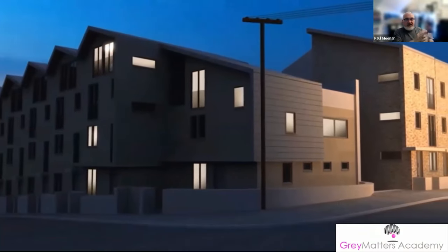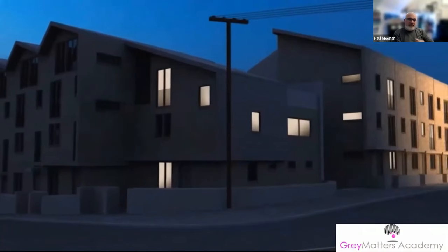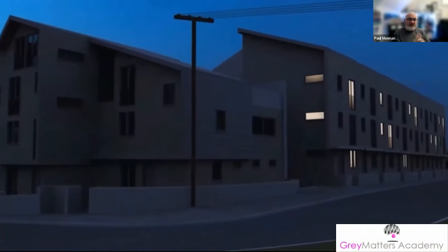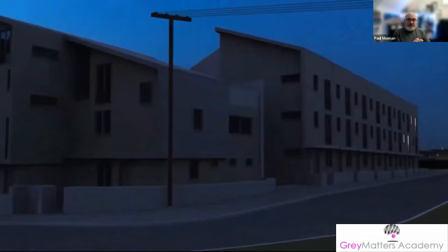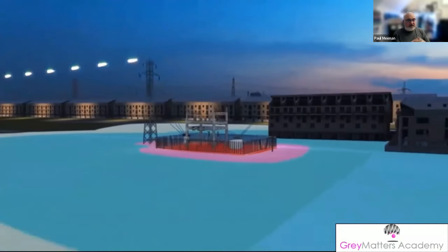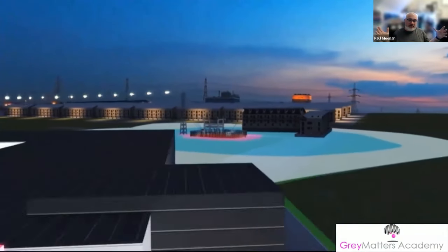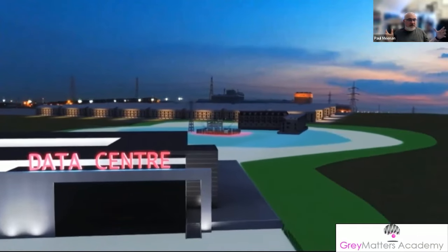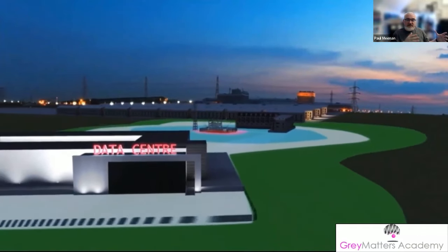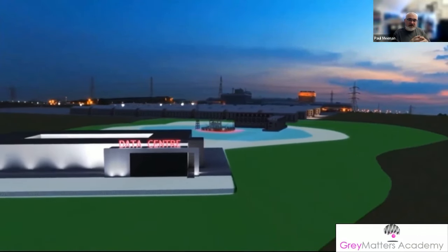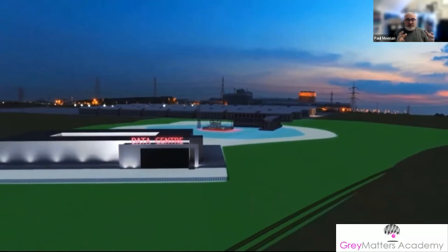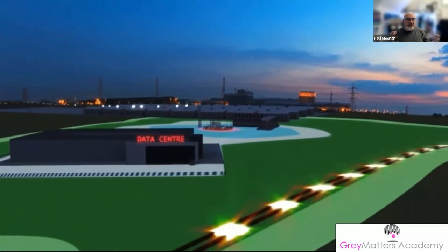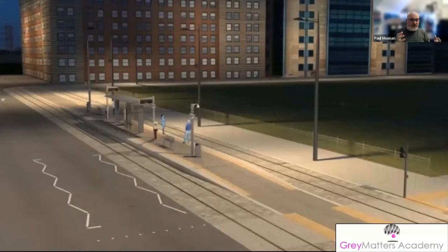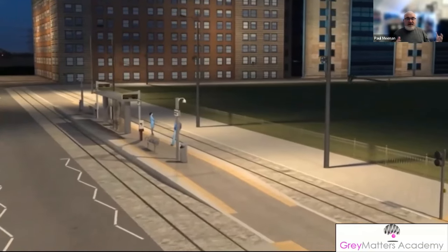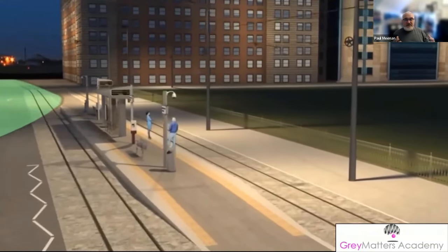Not only do the houses lose their power supply, which nobody wants, but it often happens in a lot of HV installations where there are faults, that the earth potential continues to dissipate through the ground. And this is where earthing and bonding is really important, because with critical systems like data centers, that energy dissipating through the ground could appear on earthing systems and could cause damage. It could cause damage to cables that are nearby. It could cause step or touch potentials.